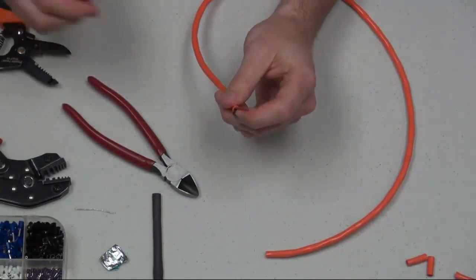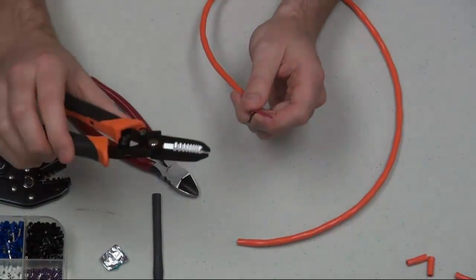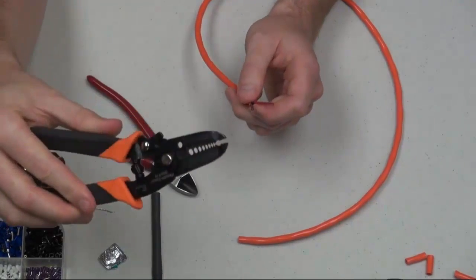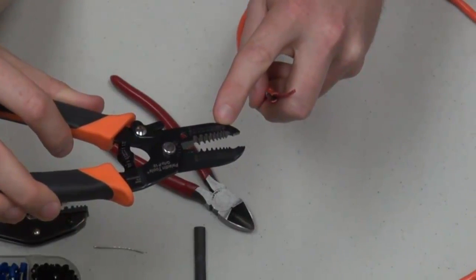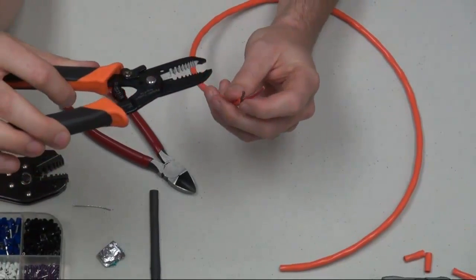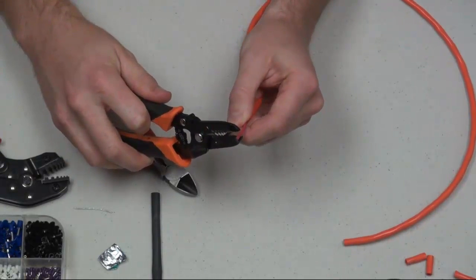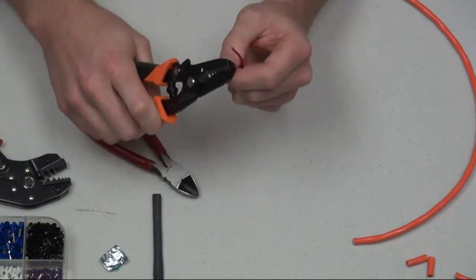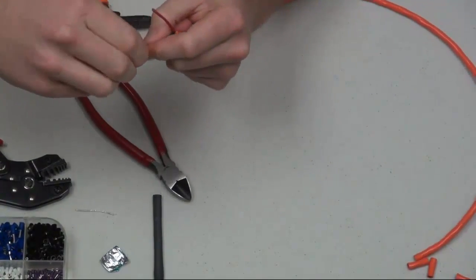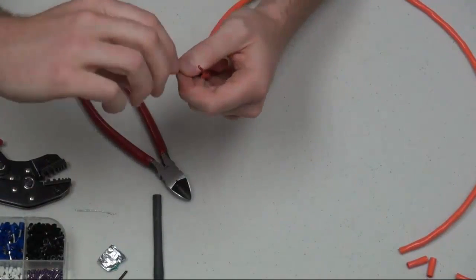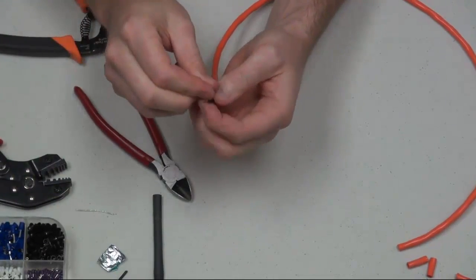The next step is to also peel back the jacket on the inner cables. So you're going to get yourself some nice wire strippers. These are really great strippers. They're fast. They're easy. They all have different gauging right on the sides here, so you know exactly what you're going to be clipping at. In this case, this wire is all 18 gauge. So I'll put it right here in 18 gauge. And you'll want to clip about, I'd say, half an inch back, just enough to get the wire ferrules on there. So you get two quick clips like that. Pull back the shield just a little bit. And then you can actually separate it fairly easily by hand. I like to go ahead and, at this point, give it a little twist with my hand. Make sure I keep those tight while I clip this other jacket back as well.